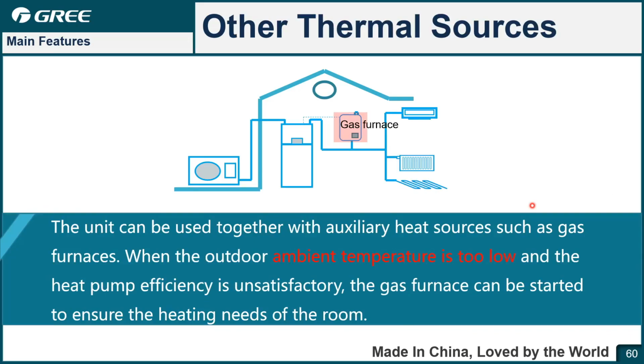Next one is the other thermal source. Other units, the water tank and the water pipe, that's the heat pump and water circulation. However, if the customer needs a boiler as a backup, they can connect it with the water pipe and use a cable to connect with the PCB of the unit, then they can be controlled together. If the ambient is very cold and the heat pump capacity is not enough, the unit can start the boiler as a backup to supplement the heat to the system and keep the capacity.